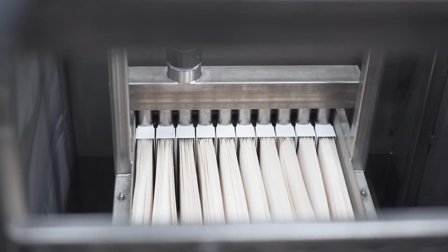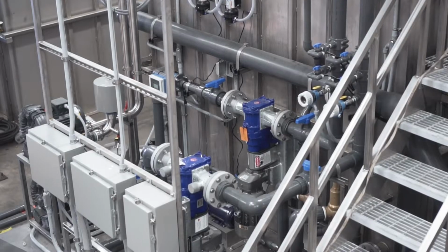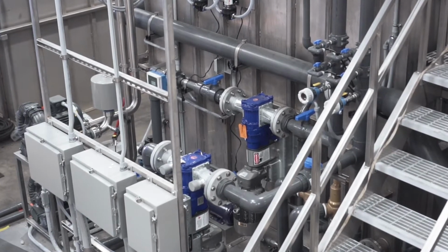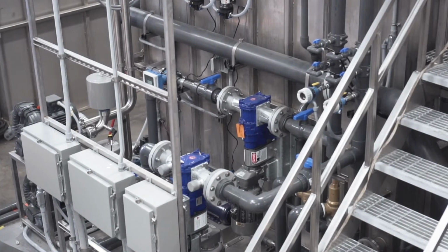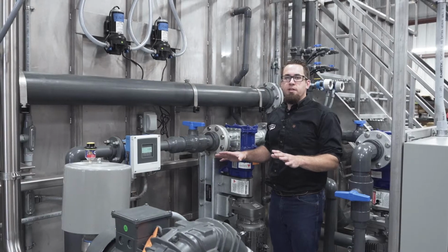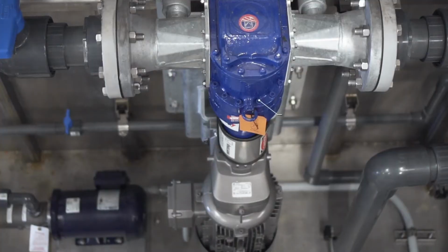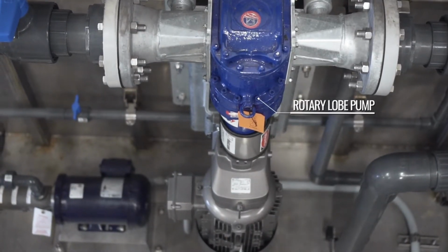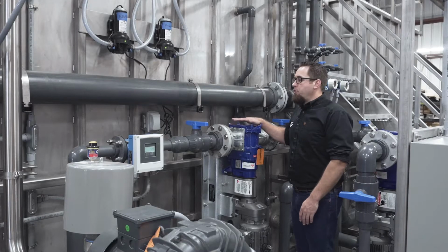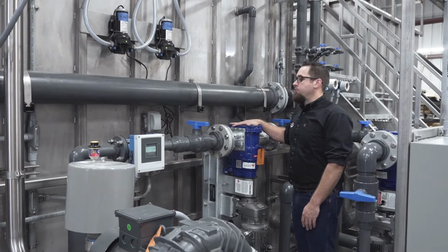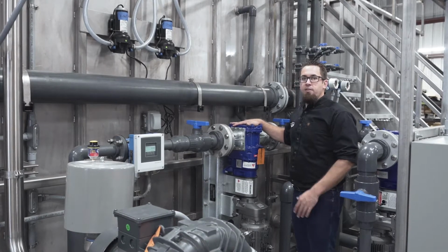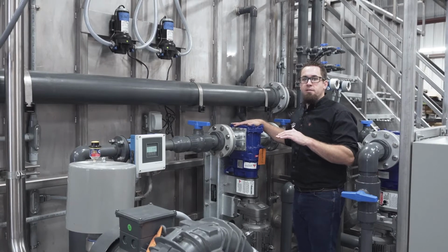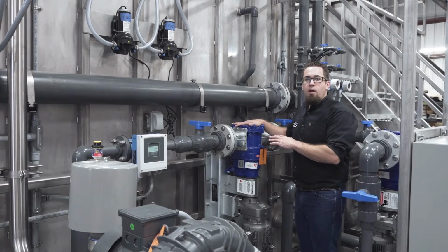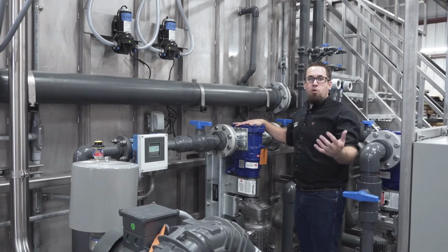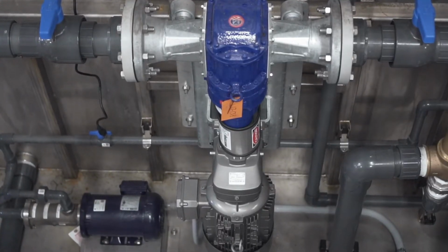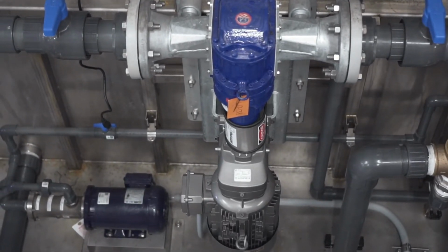Because the membranes are the heart of a membrane bioreactor, we take extreme care in all of our design in terms of the membrane permeate system. I wanted to talk about some of the features and the differences between us and what you may be accustomed to. We use rotary lobe pumps for every single one of our permeate applications. We do this for a couple of reasons. The first one is that you get the absolute best TMP readings as a result of having a PD pump, which provides both the forward or permeate withdrawal in the event that your particular membrane actually does have a back pulse.